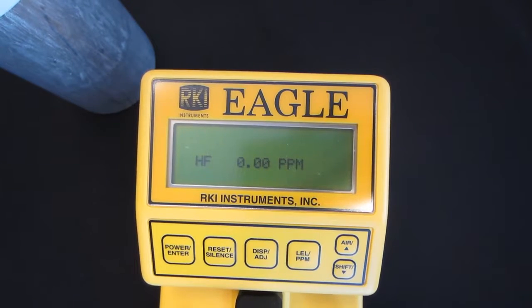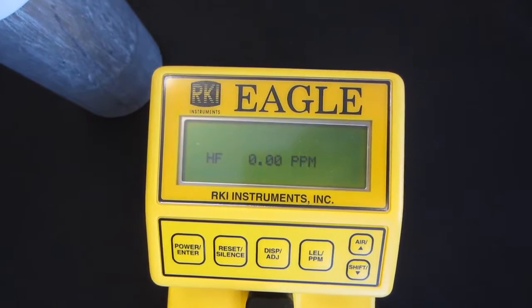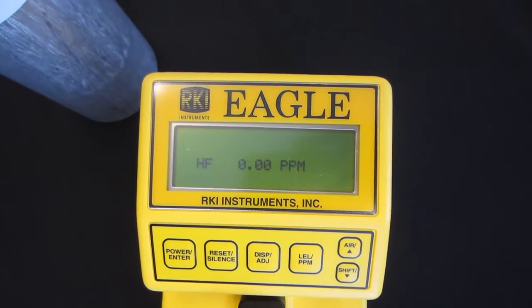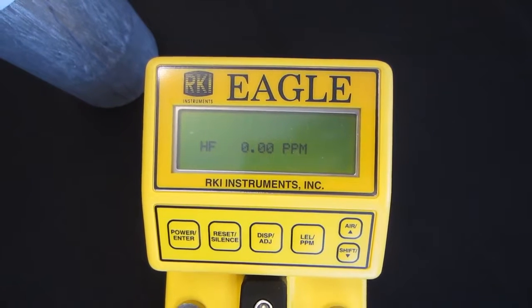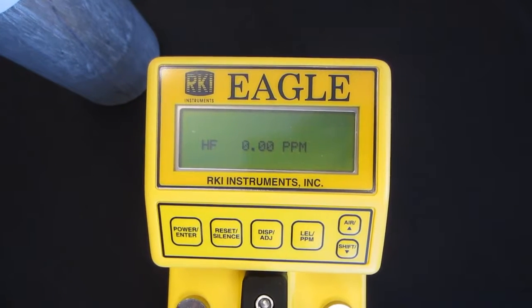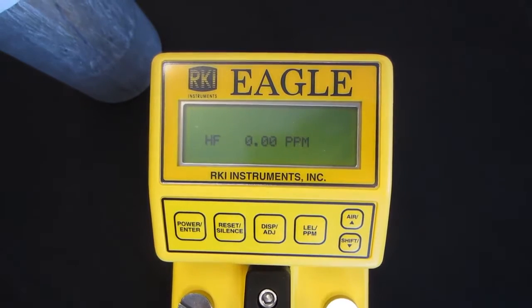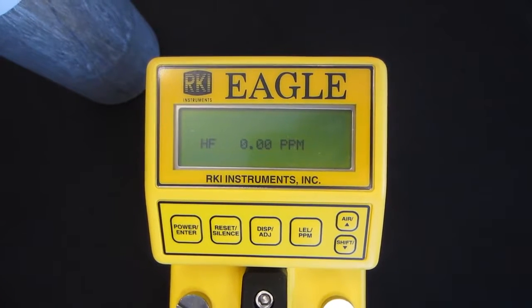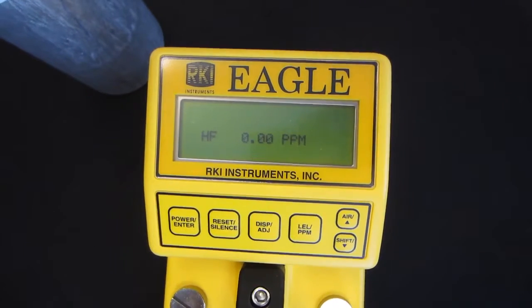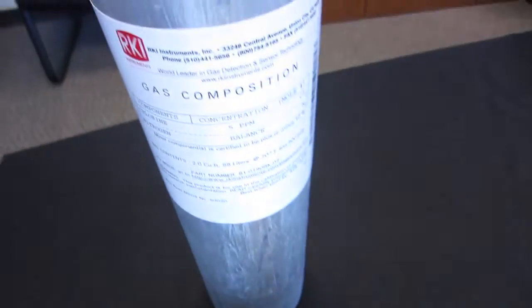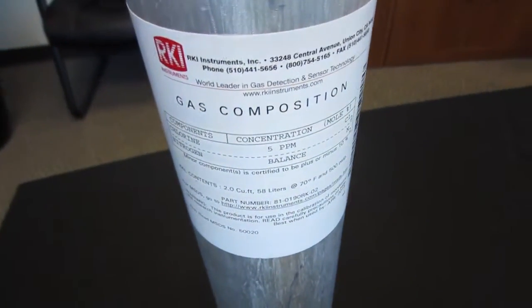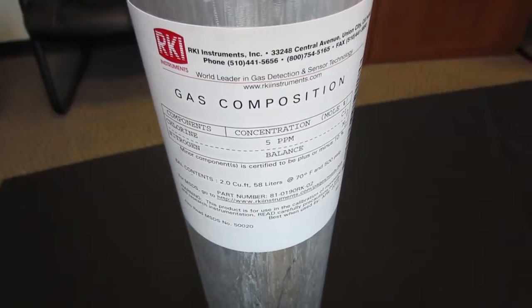The HF sensor in the Eagle has a conversion factor of 1.6. So basically that means chlorine times 1.6 equals HF. Since we're using 5 ppm of chlorine, 5 times 1.6 is 8. So that's where we had set our span in the Eagle to read 8 ppm when chlorine was applied at 5 ppm. So again, we're properly calibrated.